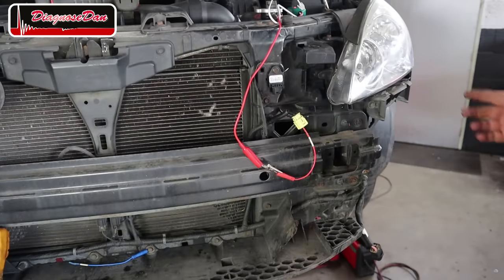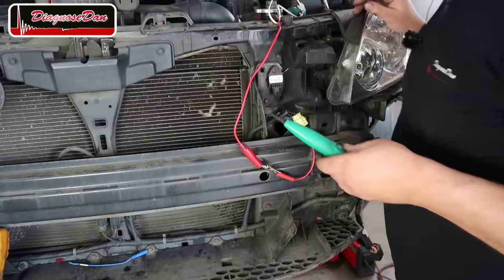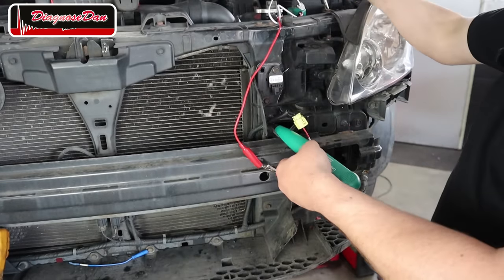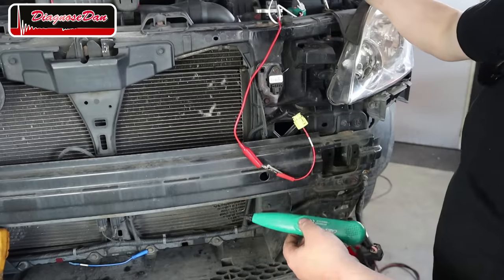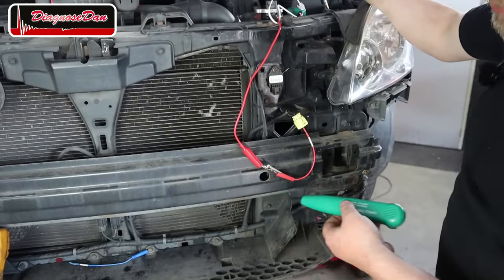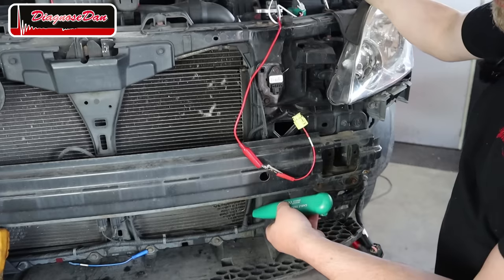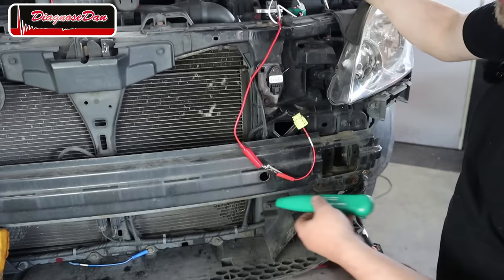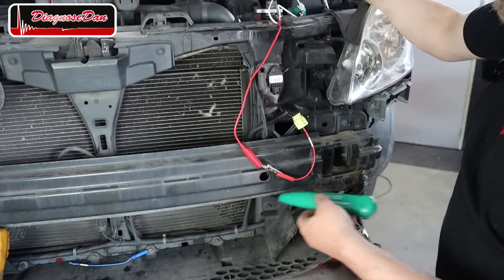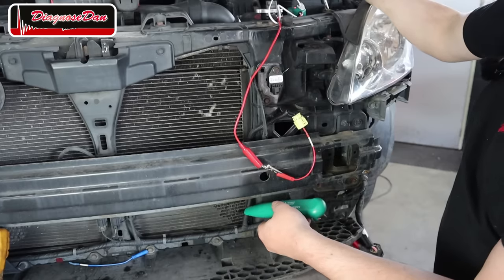Now, I really hope the microphone is gonna pick this up, but I hooked up the tone generator to that green wire and this is what that sounds like. Now, let's try it over here and exactly the same sound. Now, let's try it over here and the sound sounds a lot dimmer. Now, listen really carefully to the difference. The tone is a lot louder over here.